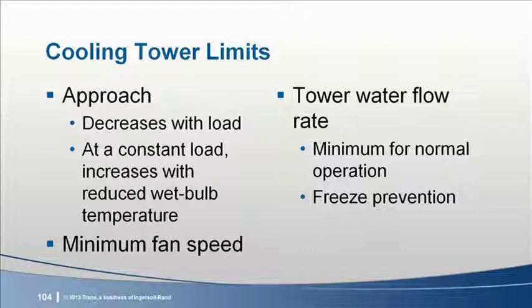Probably the most important limit to consider is the minimum tower water flow rate. During normal operation, if flow over the tower drops too far, there's poor water distribution over the tower fill. Poor distribution leads to poor heat transfer and perhaps scaling. Another possible issue is when it's cold outside, too much tower heat transfer can result in ice formation. Follow the tower provider's guidance to keep this from occurring. Now, to their credit, today's tower providers are offering more options for reducing water flow rates while maintaining good heat transfer. So there are more alternatives for reduced flow today than there were even 5 or 10 years ago.